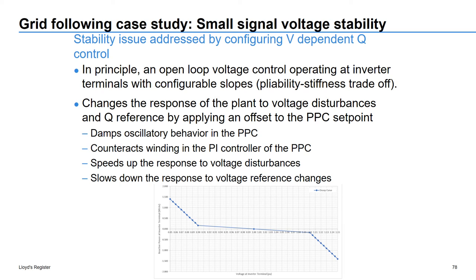We looked at this as essentially a control tuning problem. And a tool that we used here was a mode of control offered by the OEM, which gives you Q as a function of V with a variable droop slope. By adjusting this slope, it effectively gives you a trade-off between what might be considered a more stiff response, where there's a very aggressive Q response to a small change in voltage, to a more pliable response where the changes in Q are more gentle.